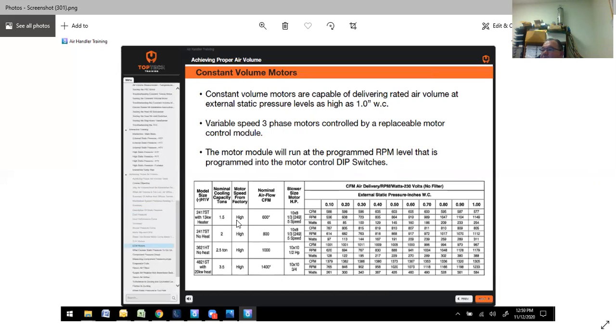So we'll just come over here and say we'll go to 3.5 ton. At 0.1, we're pushing 1379. Yeah, that's actually not bad. If we go to 1.0, we're at 1305. It's not terrible. Usually it's a little more dramatic than that, but you do actually increase your power consumption, and your airflow will reduce.